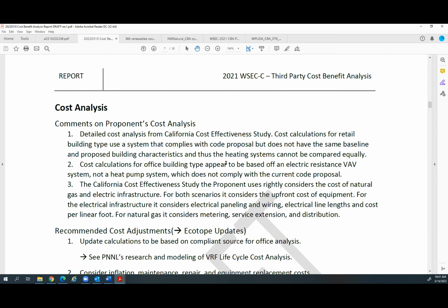Also, something to consider with this statement is the life cycle costs of the heat pump equipment. If you have a compressor that is now working to provide heating and cooling, therefore you're providing twice as much runtime on that compressor than a gas unit, I would think you could expect to see half the service life on that equipment. And so one of my questions for you, Henry, is, is that reflected somehow, that decreased service life of a heat pump versus maybe a gas pack unit? Is that reflected anywhere in the analysis?